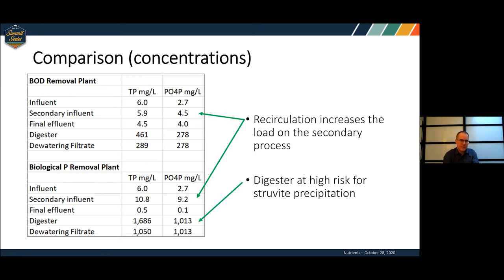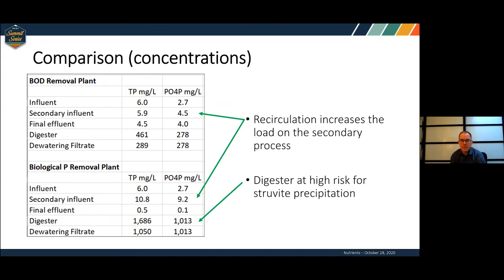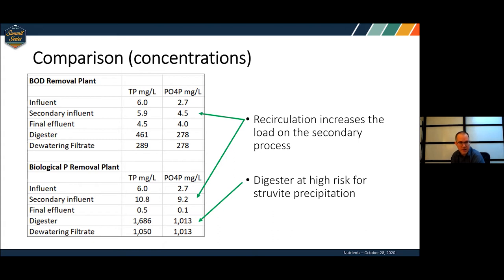Looking at concentrations: with the BOD removal plant at the secondary influent, we've got 4–6 mg/L of phosphorus. Shift to bio-P and we're double — 9–10 mg/L. That makes it much harder to meet a phosphorus regulation. Down in the biosolids system, if you've got concentrations of 1,000 mg/L of PO4-P, you're going to have massive struvite problems. This shows how you can use this tool to compare a couple of situations.